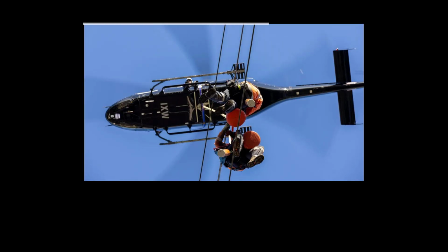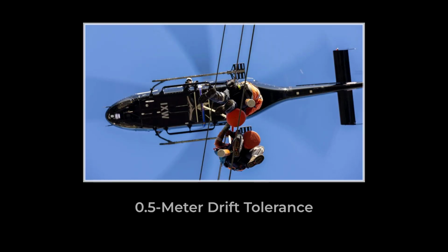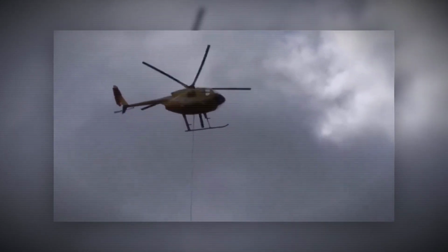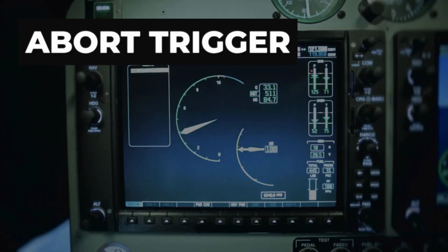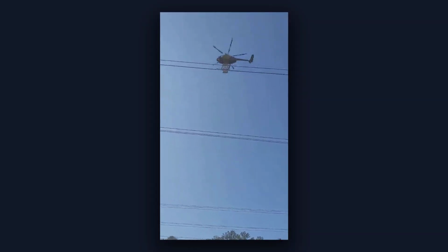The pilot must maintain lateral drift within a 0.5 meter margin, using visual references and onboard sensors to keep the helicopter's position stable relative to the conductor. This tolerance is enforced by automated alerts, and any deviation beyond the set envelope triggers an immediate abort.